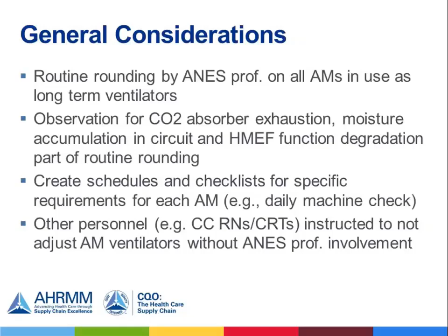In particular, the most significant difference between an anesthesia machine and a CCU ventilator is the fact that the anesthesia machine recirculates gas. It's a rebreathing system. And as a result, we use carbon dioxide absorbers, and all of this is designed to maximize the efficiency of the machine and to minimize the waste of rather expensive volatile anesthetic agents. And so there are a lot of parts of the machine that are not present on a CCU ventilator. So it was an issue of creating schedules for people to round on these machines and to evaluate them.